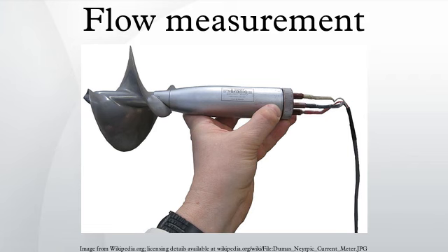Calibrated cone meters have an uncertainty up to ±0.5%. Uncalibrated cone meters have an uncertainty of ±5.0%.